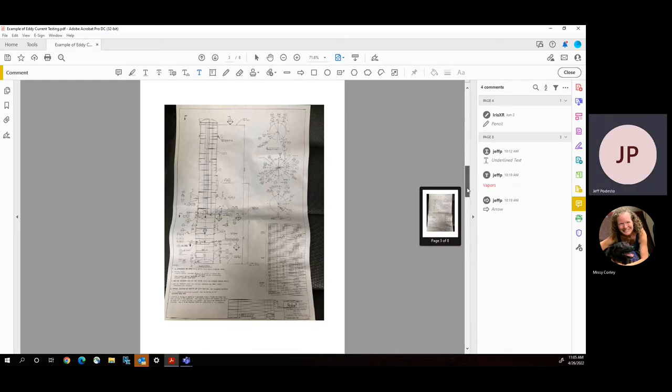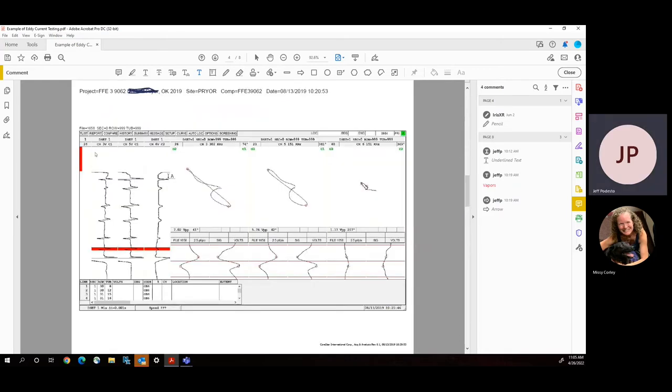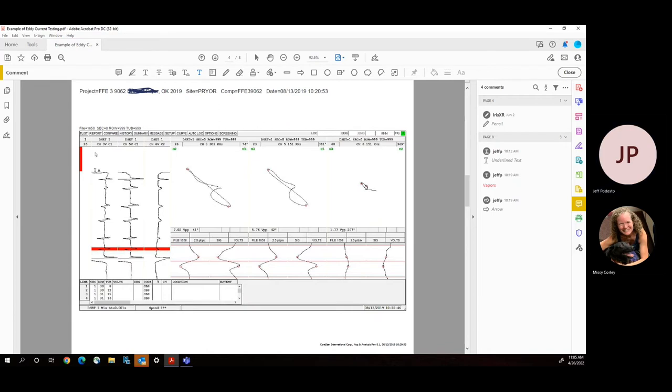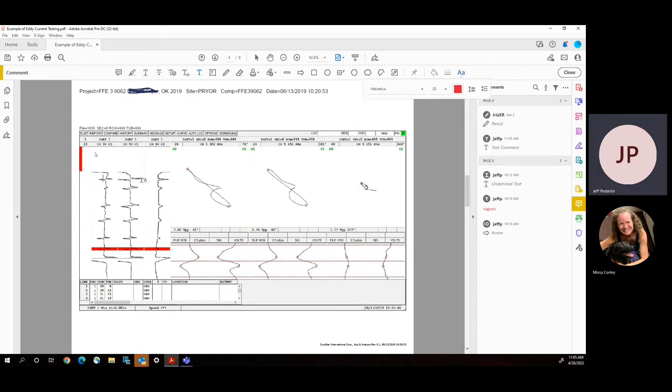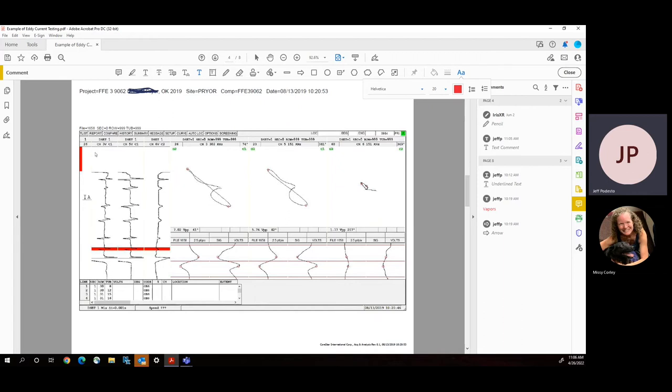The feedback that we get looks something like this. And though it's not something that really means a lot to the layman, it does tell the technician what's going on in each one of these tubes. This is actually three different tubes, one tube here, one tube here, one tube here. This is the top of the evaporator. As it drops down, you get these little deflections, and each one of these deflections is some type of data point that the technician or the software package can determine what type of flaw might exist at each one of those deflections.